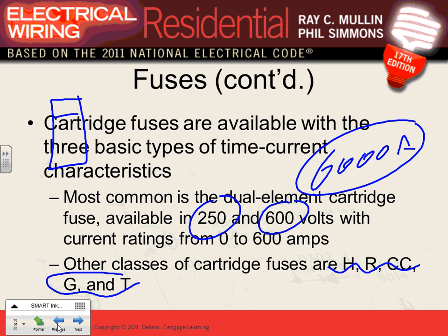Here's my fuse. I have, let's just say, a 32,000 amp short circuit here. This is, say, 100 amp, and the interrupting is 45 kiloamp. I bought a fuse 100 amp with an interrupting 45 kiloamp. A short circuit right here is 32 kiloamps. Would this blow? First of all, would this blow? If the short circuit here is 32.